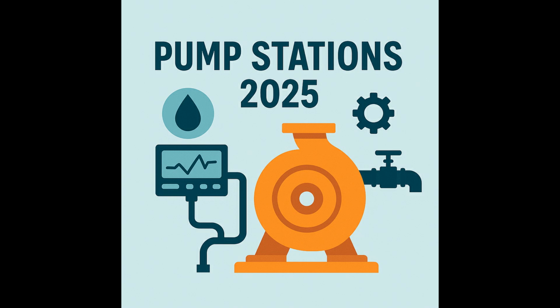That sounds nasty. So how does the pump flow rate tie into this NPSH margin and the risk of cavitation actually happening? Flow rate has a direct impact. At low flow, suction conditions are usually pretty stable, but efficiency is poor, and you can still get recirculation issues causing damage. The NPSH margin might technically be higher, but you're not necessarily safe. Crucially, though, at high flow, when you go beyond the best efficiency point, the NPSHR, what the pump needs, increases sharply because the pump just needs more suction energy to handle that flow. If the NPSHA, what the system provides, doesn't rise accordingly, that vital margin shrinks, sometimes drastically. And that leads to a much, much greater risk of cavitation.